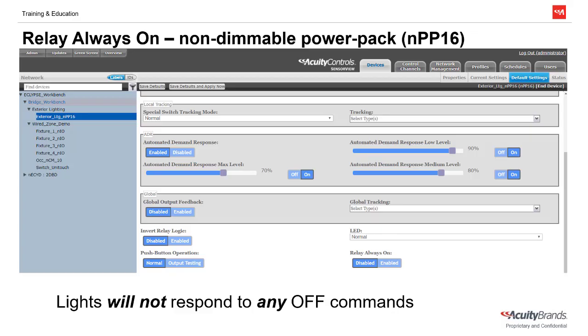Something to note: if you're programming a non-dimmable relay or power pack, you will not see the Dimming Always On setting. You will only see the setting Relay Always On. If enabled, the relay will not switch off under any circumstances.